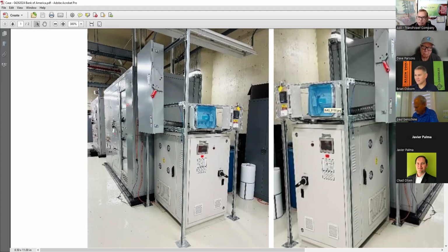It is beautiful. No, that does look like a clean installation, Adil. Just to clarify, so they're using the disconnect switch as the required disconnect for that piece of equipment. Is that disconnect switch coming off of a circuit breaker, or did they do a direct bus tie for that installation? That is a direct bus tie. Okay, direct bus tie. And then the overcurrent protection in this particular case is in the MPTS. MPTS has all the protections, and there are fuses in this disconnect. They have fuses. Okay, so it's a fused disconnect. It's a fused disconnect. That's why it's so big.